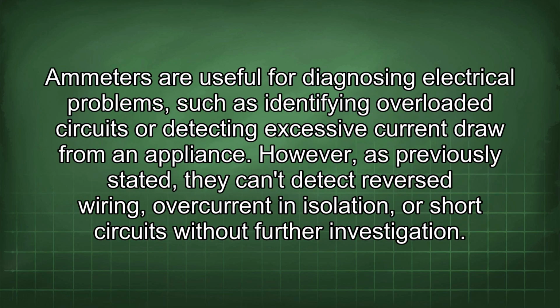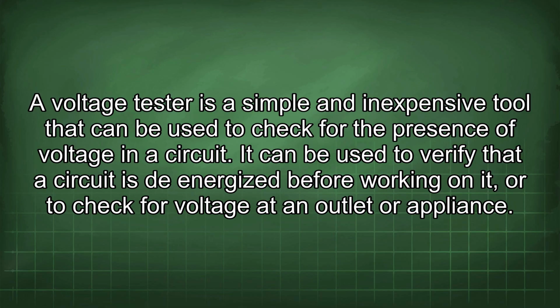Ammeters are useful for diagnosing electrical problems, such as identifying overloaded circuits or detecting excessive current draw from an appliance. However, as previously stated, they can't detect reversed wiring, overcurrent in isolation, or short circuits without further investigation. A voltage tester is a simple and inexpensive tool that can be used to check for the presence of voltage in a circuit. It can be used to verify that a circuit is de-energized before working on it, or to check for voltage at an outlet or appliance.